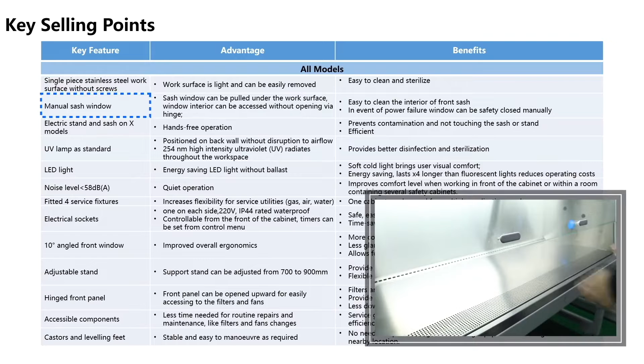Now, all models feature a single stainless steel working surface. This is normally 304 as standard. However, we can offer 316 steel, which is slightly more corrosion resistant if you're using very oxidizing cleaning agents. Highly oxidative cleaning agents like chlorine dioxide or Virkon can actually rust 304. In the dual HEPA model, we have, in the 1200 anyway, a 3-piece stainless steel working area. This means it's easier to remove any one piece for cleaning. All cabinets come with a manual sash as standard. Now the X models do have options for electric sash and stand, but I'll go into that next. The manual sash is much more reliable as there are no electronic components to fail, and in the event of a power failure, you can easily close the sash.